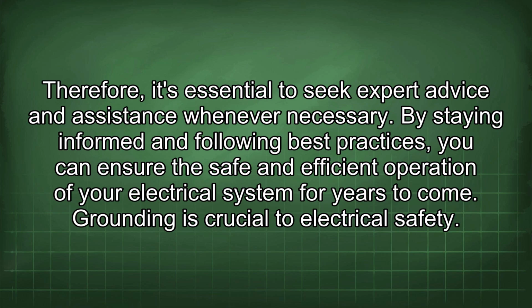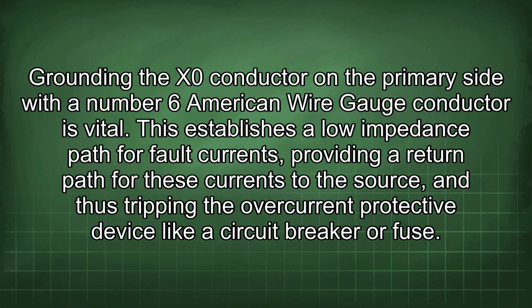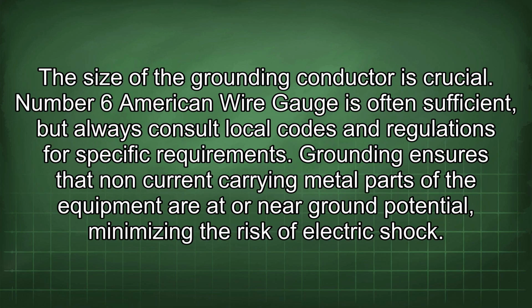Grounding is crucial to electrical safety. Grounding the X0 conductor on the primary side with a number 6 American wire gauge conductor is vital. This establishes a low impedance path for fault currents, providing a return path for these currents to the source, and thus tripping the overcurrent protective device like a circuit breaker or fuse. The size of the grounding conductor is crucial. Number 6 American wire gauge is often sufficient, but always consult local codes and regulations for specific requirements.